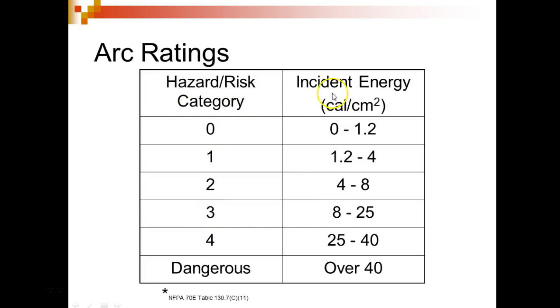And this shows you the risk categories, calories per centimeter squared. And like I said, I've seen the equation somewhere, but the actual risk hazard is going to be 0 through 4. And anything over 40 is labeled as what? Dangerous. So we're down in this category here. This is the category that we're in in motor controls because of where we're at. Okay?